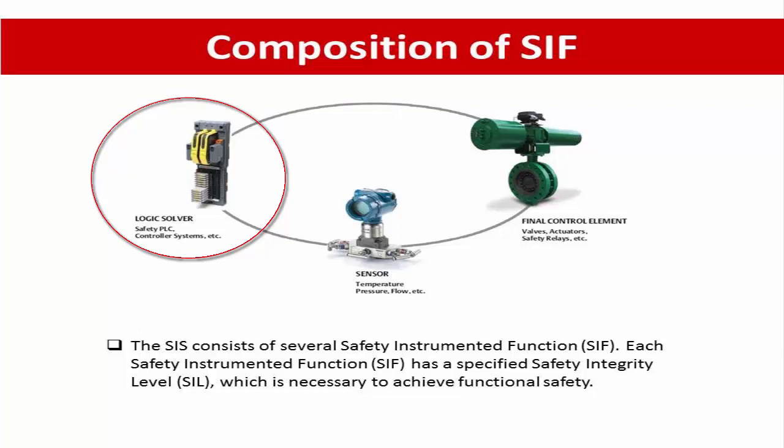The second element is the logic solver, which is designed to determine what action is to be taken based on the information gathered. It typically uses a controller that reads signals from the sensors and executes a pre-programmed action to prevent a hazard by providing output to final control elements.